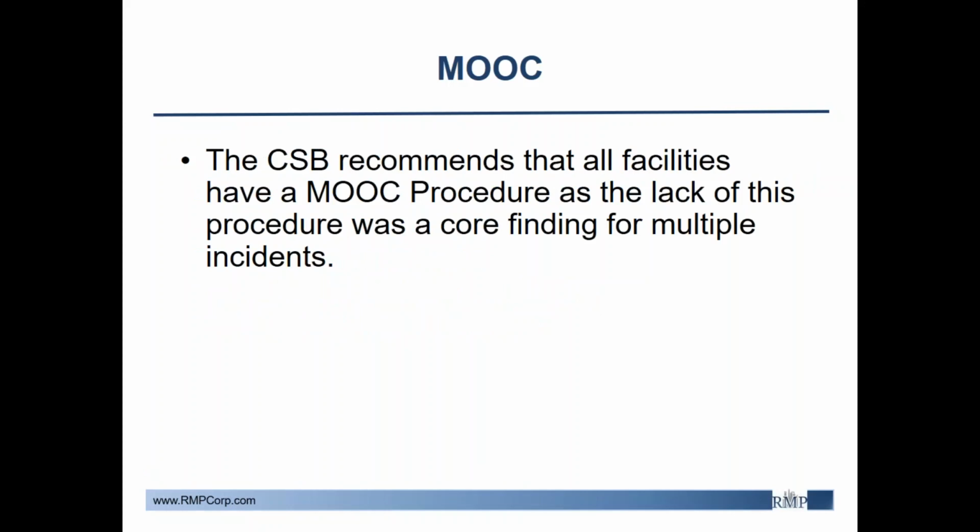So the CSB recommends that all facilities have a MOC procedure, as the lack of this procedure has been a core finding for multiple incidents. So the key takeaway here is even if you're not a refinery, this is something you should consider doing. MOCs currently do require an MOC on organizational changes, which Morgan touched on a little bit, and that affect the covered process. So that's the key caveat there: if your organizational change will affect your covered process in some way, you should do an MOC on it, and it's flagged by OSHA PSM in a 2009 interpretation letter.